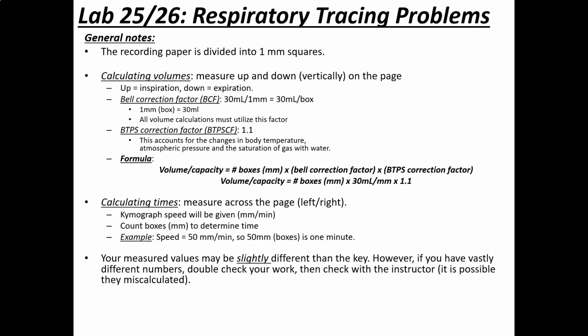As I mentioned before, we also need the BTPS correction factor. And we're just going to assume it's 1.1. And that's again body temperature, pressure, and saturated. That's what the S stands for. And that's the saturation of your gas with water.